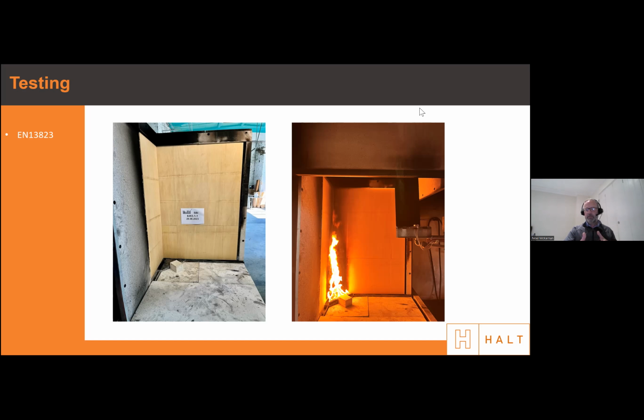So in this case, the plywood's cut up, and that's a key element, because when plywood is generally fitted on site, there will be cuts made to that material. Impregnating timber, as you saw in the previous slides, deposits the fire retardant into the very cell structure of the timber. So there are essentially no limits to what you can do - you can cut it, you can sand it, you can drill holes in it. This goes back to how it was tested in its field of application.